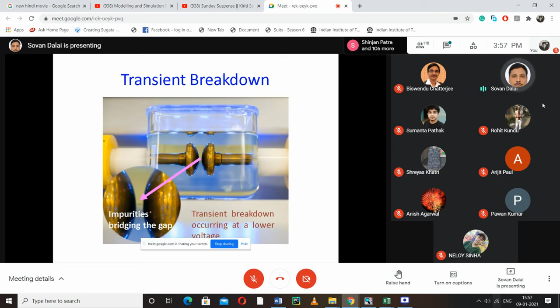Before going to the demonstration with the app, I want to mention some basic rules you have to follow. IS 6792 states that you have to increase the voltage at 2 kV per second. The test must be carried out 6 times on the same cell filling. For transient breakdown, the reading is taken when the first spark is seen. This is the complete result table, and this is the average breakdown strength. This average breakdown strength is equivalent to the average breakdown voltage, because we maintain the same gap spacing throughout, so you do not mention it as breakdown voltage per unit length.